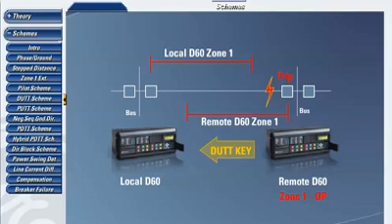This is where the term underreaching came from, because the keying signal is initiated by identifying a fault within the relay's underreaching zone 1. As soon as the local relay receives the DUTT key from the remote relay, it will immediately trip its breaker, thus clearing the fault on the transmission line. The important thing to note with this scheme is that the local relay will trip as soon as it gets a transfer trip signal from the remote relay without requiring any indication of a fault within its own zones of protection, hence the term direct transfer trip.